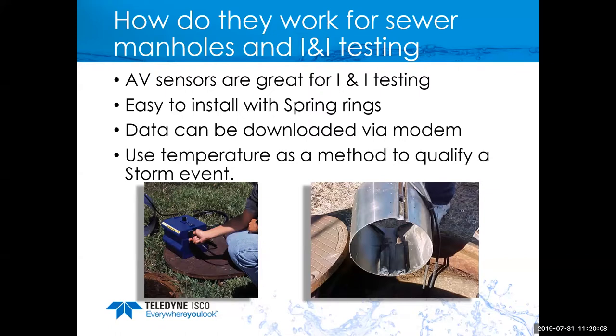Another thing about the 2150 area velocity sensors that you may not know about is that the sensor reads temperature, and it uses that to compensate the level calculation for temperature changes. And what I like to use it for is that if there's a rain event, you're going to see the temperature drop as you're getting infiltration. So you're going to notice that your level's going up, temperature starts dropping, and it's just one way to confirm that you're having a rain event.